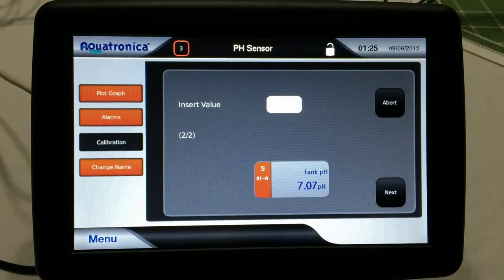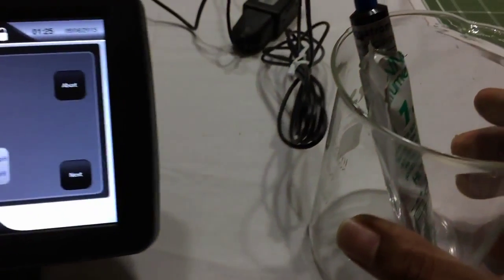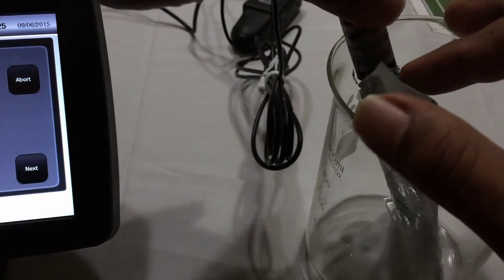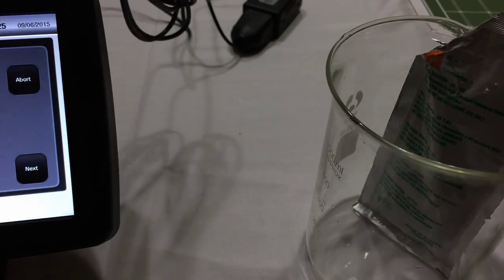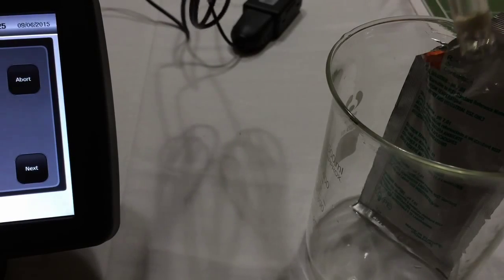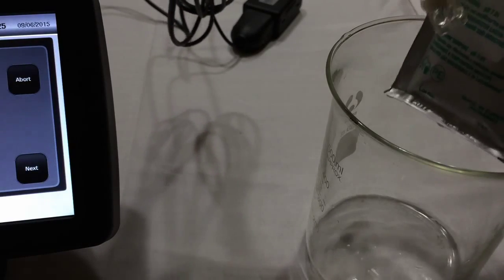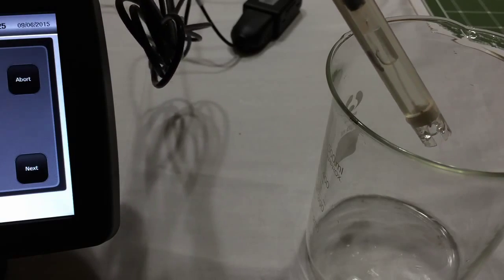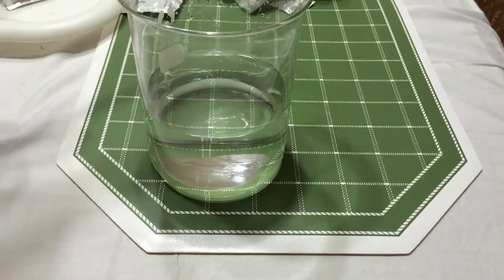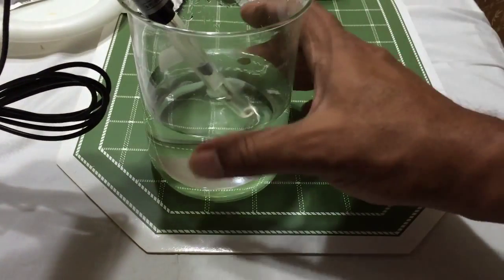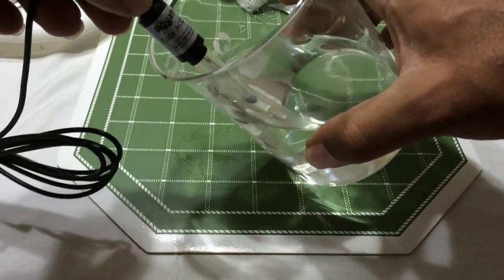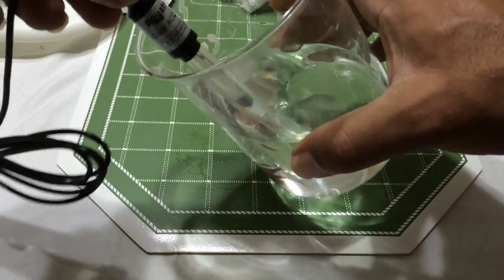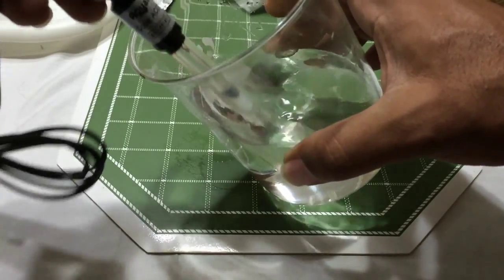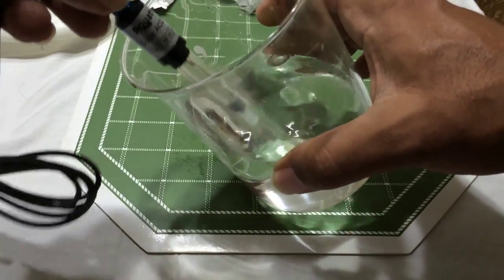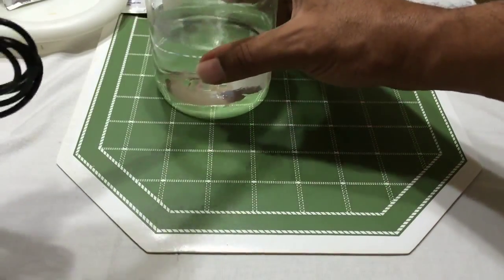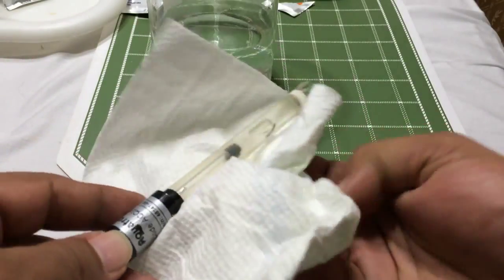So the next thing I'm going to do is go over, get the beaker, take the probe out, and I'm going to carry this over, get a little RO water, and rinse it. So I have a little RO water here, and I'm going to put the probe in, and I'll just make sure that there's no fluid left over from that. Rinse it a little bit, shake it around, don't bump the probe onto the glass, and when that's done you pull it out and you dry it off.